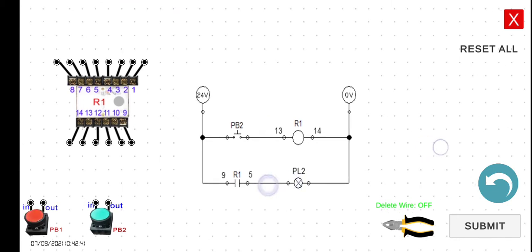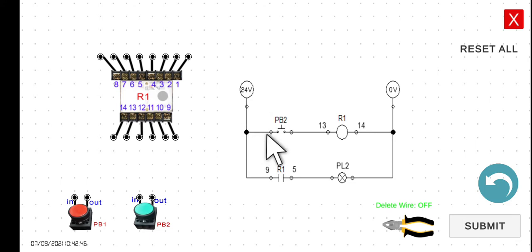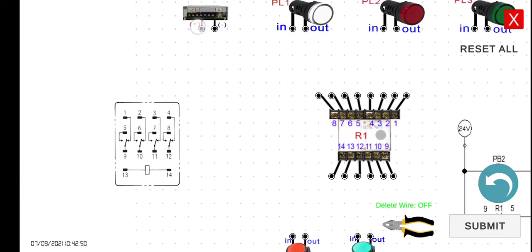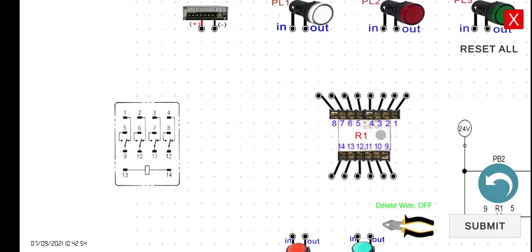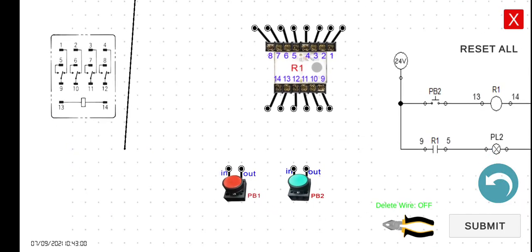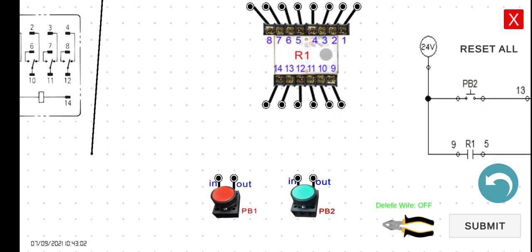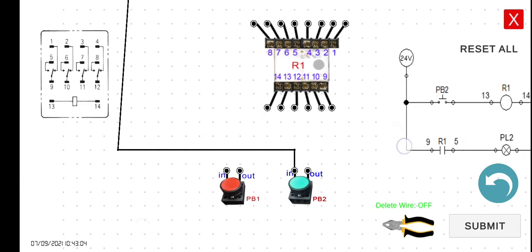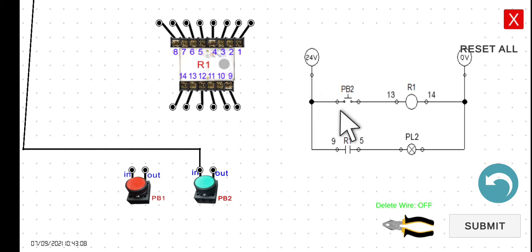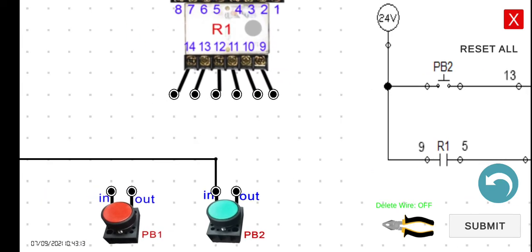Now let's wire this diagram here. Same as what we did in the previous lecture, 24 volts to the PB2, to the input of the PB2. So 24 volts to the input of the PB2. And then this one is that particular wire here. And then the PB2 to the 13, which is here. Let's zoom in.